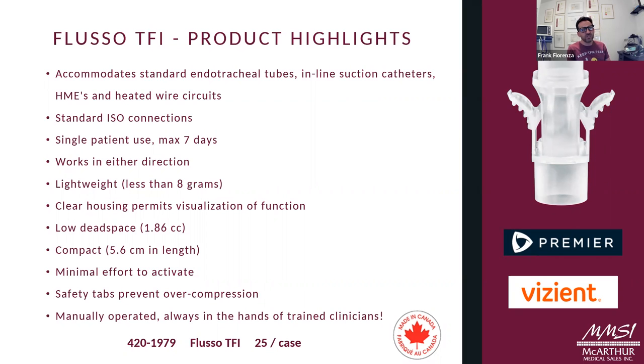This keeps it clean while we keep it hidden in our secret spots. It works in either direction since there's no valve inside; it works off a different concept, which we'll see on the next slide. So if somebody puts it in the wrong place, it will still function. It doesn't impact flow, and it's lightweight, which is one of the big differences from the bypass. It's more of a small PEEP, even neonatal, device. It's 8 grams and only 1.86 cc's of dead space, compared to 9 cc's for the bypass, and it's shorter in length as well.